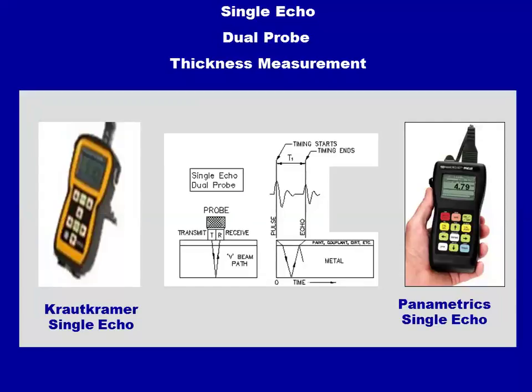Another problem with a single echo: since you're only looking at one echo, if there's a crack or an occlusion in the steel, the sound comes down, gets a partial reflection, goes back up, and stops the clock. It tells you the steel is this thick - no, actually it's this thick. There's no verification of where the sound came from or what it's doing. Is it really from the real back wall? Is it the real steel? Or just what is it?